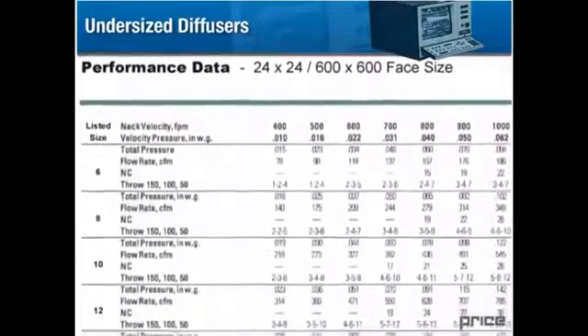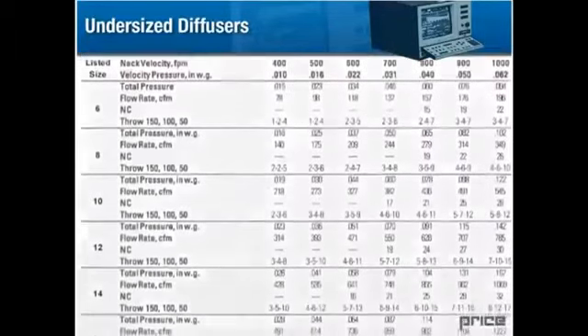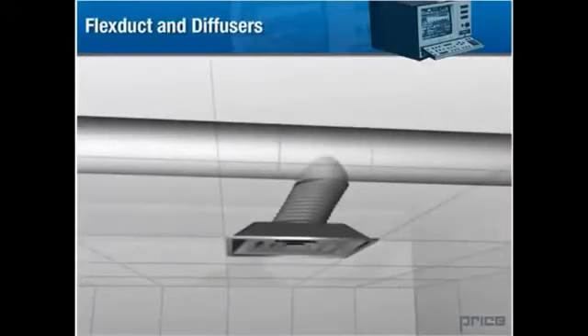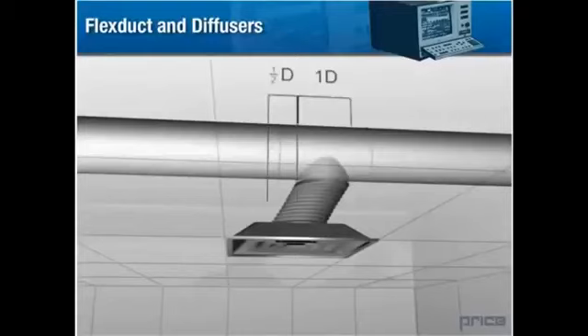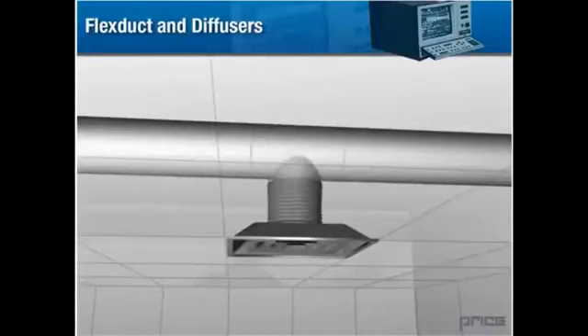Use your price catalog to refer to sizing data and NC levels. Scenario 2. Improper installation of flex duct. Another factor that can contribute to poor noise levels in a room is the improper alignment of diffusers to the supply ducts, especially when flexible duct has been used in close quarters. Skewing or crimping the flex duct by half a diameter can add up to 15 decibels to the manufacturer's noise rating. By placing the diffuser directly under the takeoff and straightening the flexible duct connector, noise levels can be minimized.